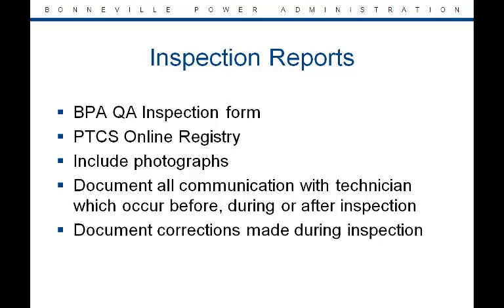BPA provides an inspection form to collect this data so that it can later be entered online. Some inspectors elect to use computers or tablets in the field for this data collection. Include photographs and document all communication with the site technician that occurs before, during, or after inspection. Document any corrections made during inspection.